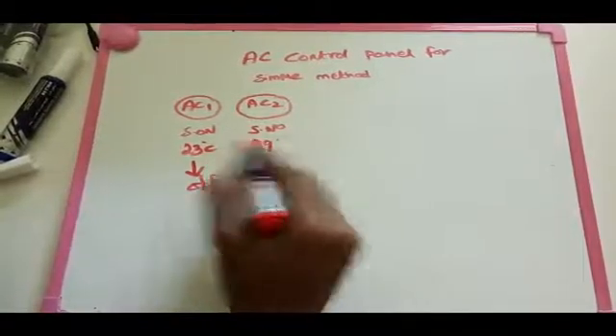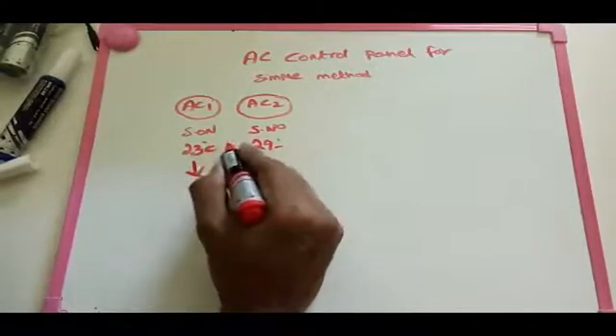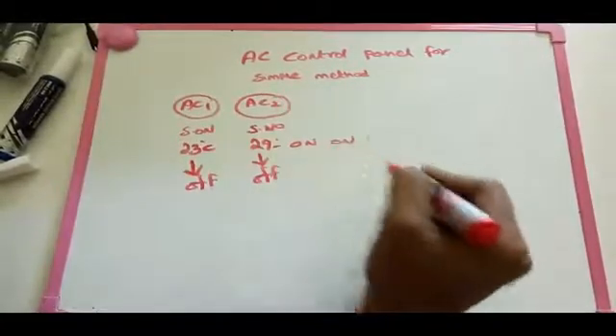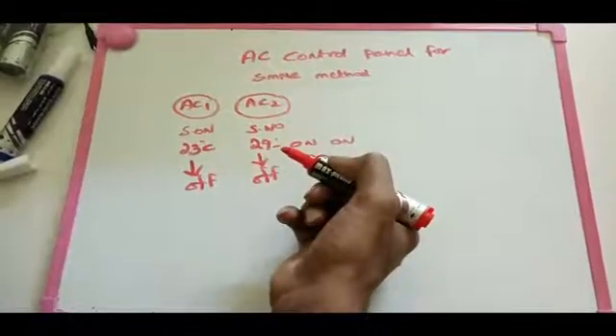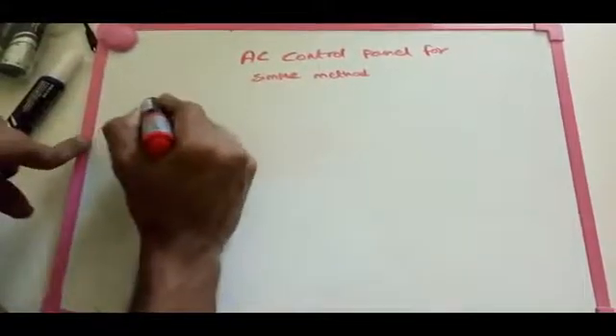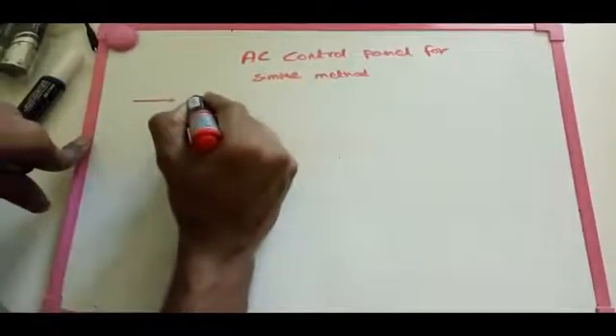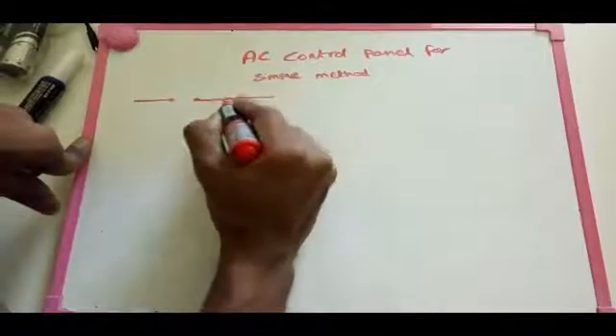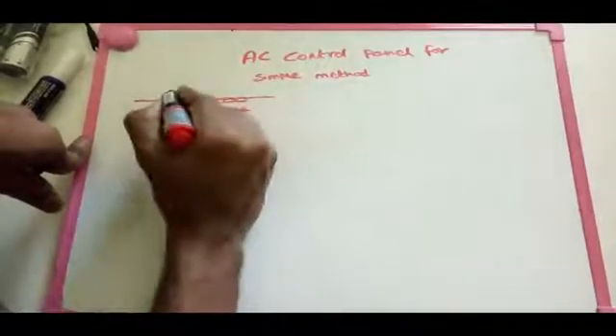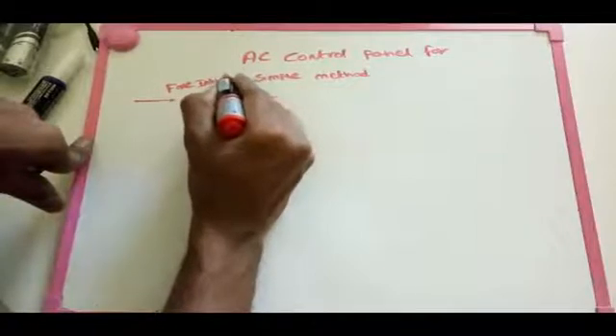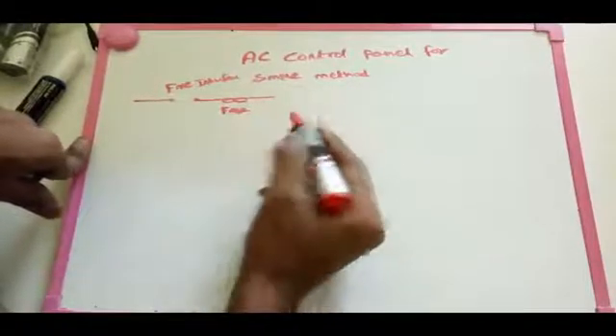Below 20 degrees Celsius, we need to switch off both ACs. That is what we need to maintain in this control diagram. Now we are going to draw the control circuit. First, here is the fire interface — meaning in any fire emergency, this interface will switch off the ACs. After that, this one is the control fuse for safety purposes.